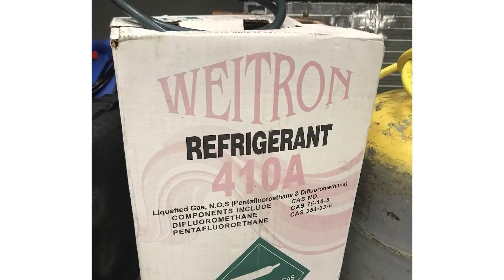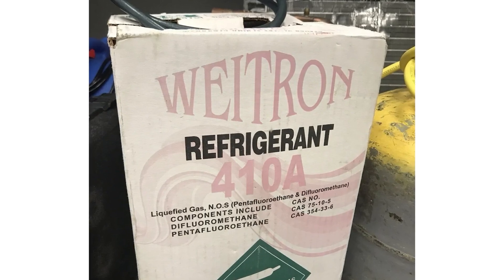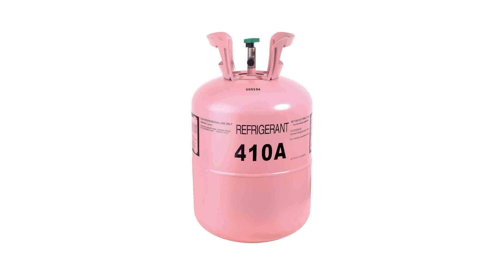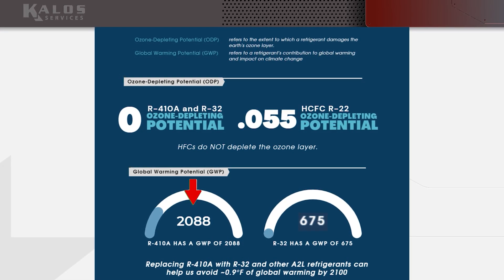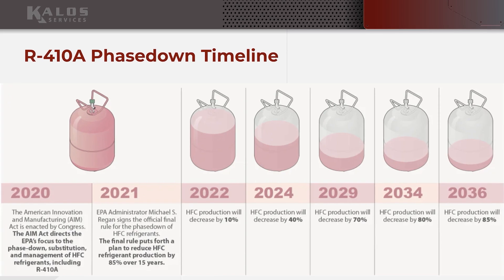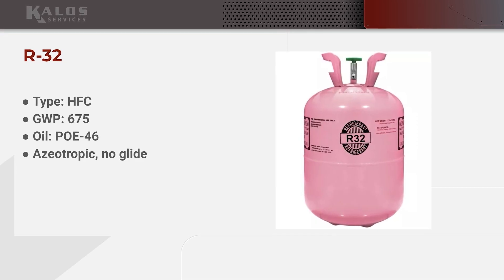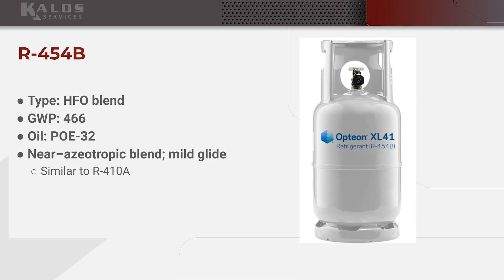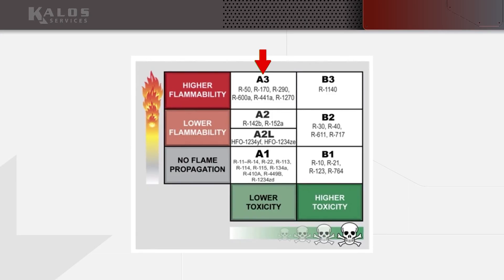Over the last 25 years, the dominant refrigerant used in residential and commercial air conditioning in the United States is called R-410A, which often went by the brand Puron — although in some cases it was still called Freon. Again, just brand names. But R-410A, because it has a high GWP, is now being phased out. And that's where modern A2L refrigerants come in. These are very mildly flammable molecules, and the A2Ls being used in the United States do not contain propane, or A3-type refrigerants.